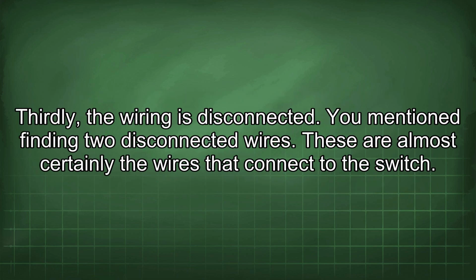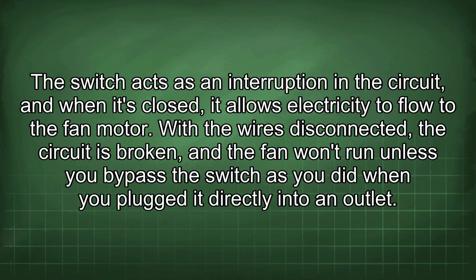Thirdly, the wiring is disconnected. You mentioned finding 2 disconnected wires. These are almost certainly the wires that connect to the switch. The switch acts as an interruption in the circuit, and when it's closed, it allows electricity to flow to the fan motor. With the wires disconnected, the circuit is broken, and the fan won't run unless you bypass the switch as you did when you plugged it directly into an outlet.